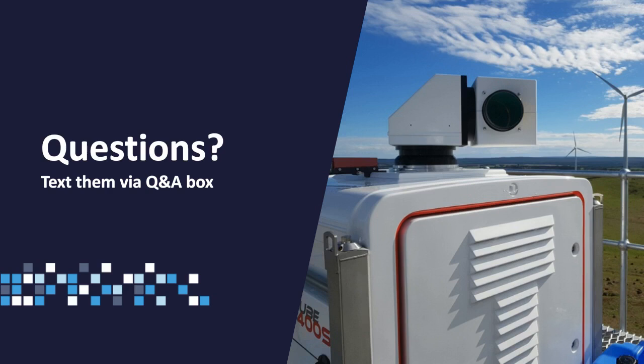Thanks, Pedro. One more question regarding when using a Nacelle-mounted lidar for power curve test without any mast, how do you measure the vertical wind and inflow upflow angle? And same question for turbulence and all that kind of other measurements. Julien? Yeah, so that's a tricky one. The LiDAR itself is based on assumptions to measure the wind, and one of the main assumptions, and that's why it's now focused on flat terrain, is that we have a flow homogeneity. So basically, the assumption here is that there is no inflow, and this is why we focus the application for now on offshore and onshore flat terrain, and that's also why the IEC is now only valid for flat terrain.